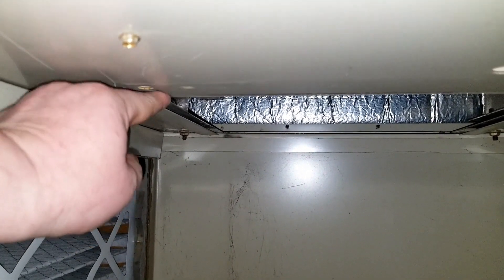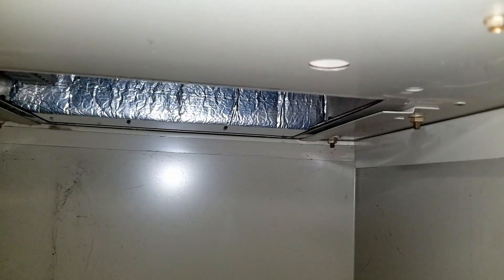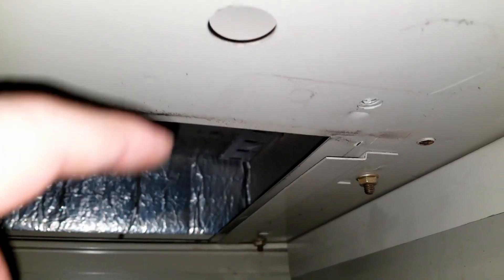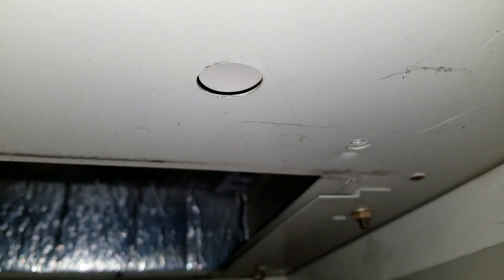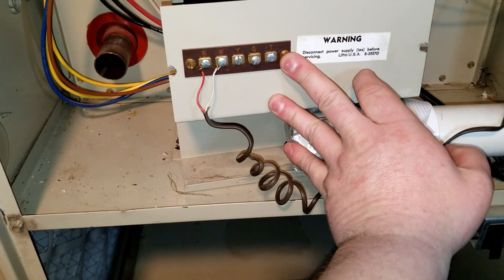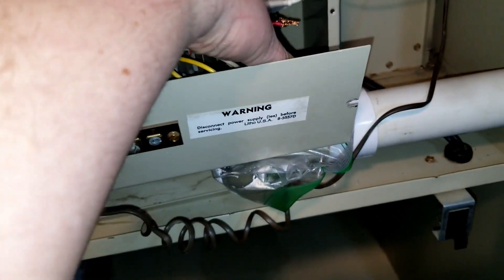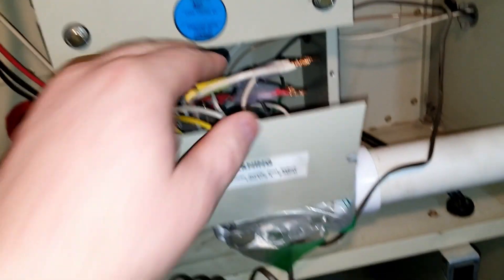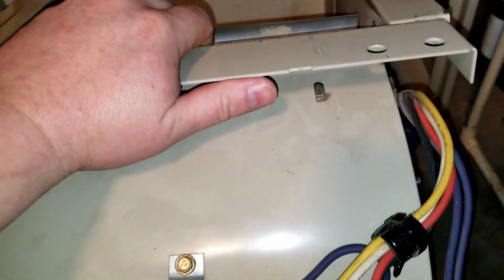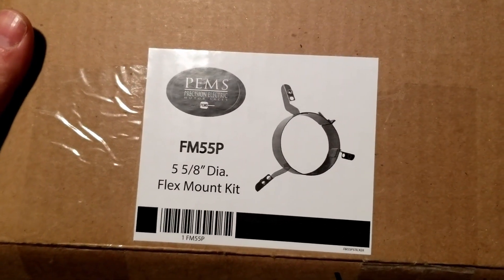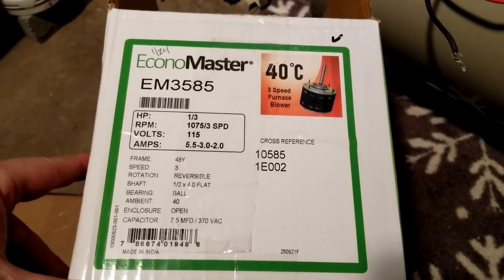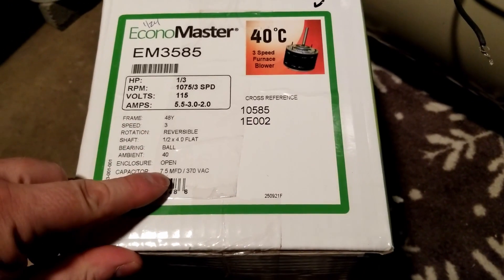Basically there's some bolt holes here. There's two bolts that hold this blower on, this little track right there is what the blower slides right into. There's one on each side, a little fin slides right into that, then two little 7/16 bolts thread into there, one there, one there. Right in here is the electrical connector grommet. Got to remove your PVC piping from there, take these two screws out, slide this out the way, disconnect your wires, pull your wires down through, and this whole blower assembly comes out. Here's the part number for the bracket Mongo got. Here's the electric motor Mongo got.